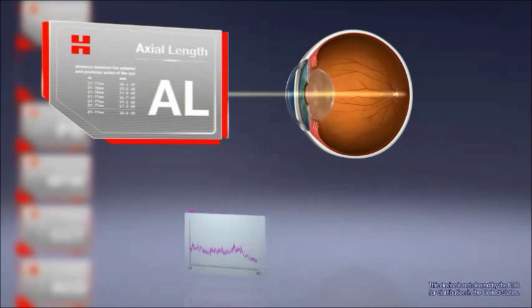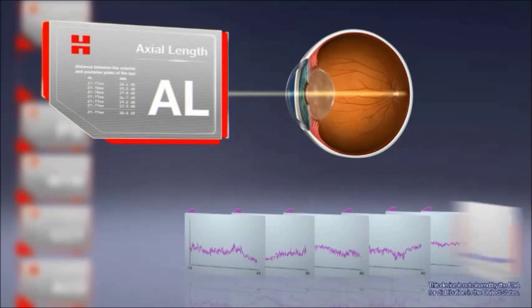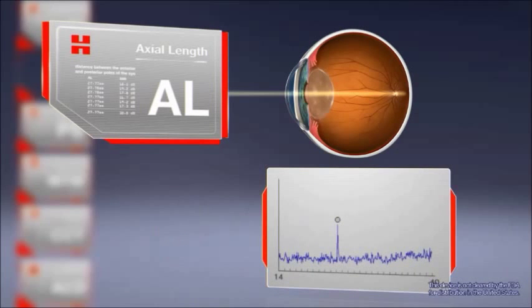Even through dense cataracts, axial length can be measured by taking multiple readings and averaging those readings using advanced algorithms which enhance the signal-to-noise ratio.